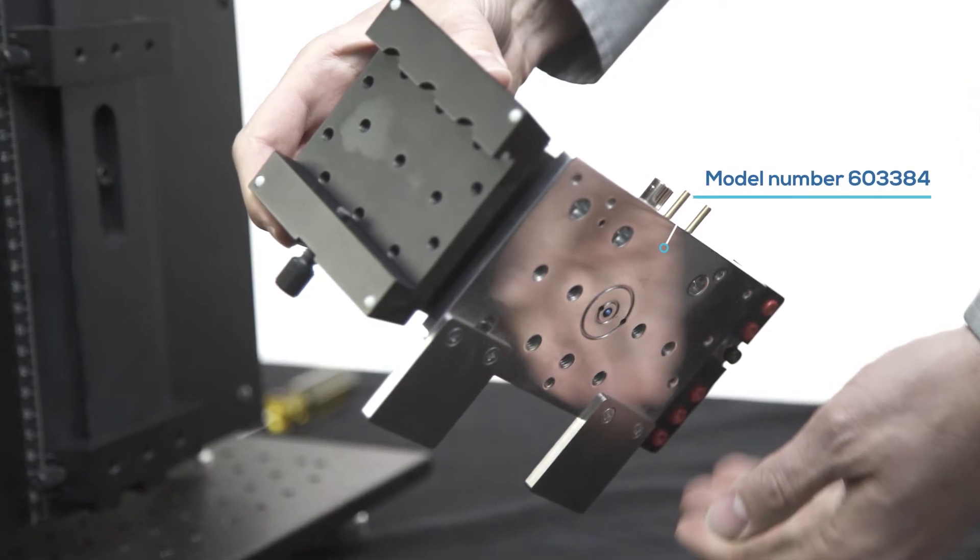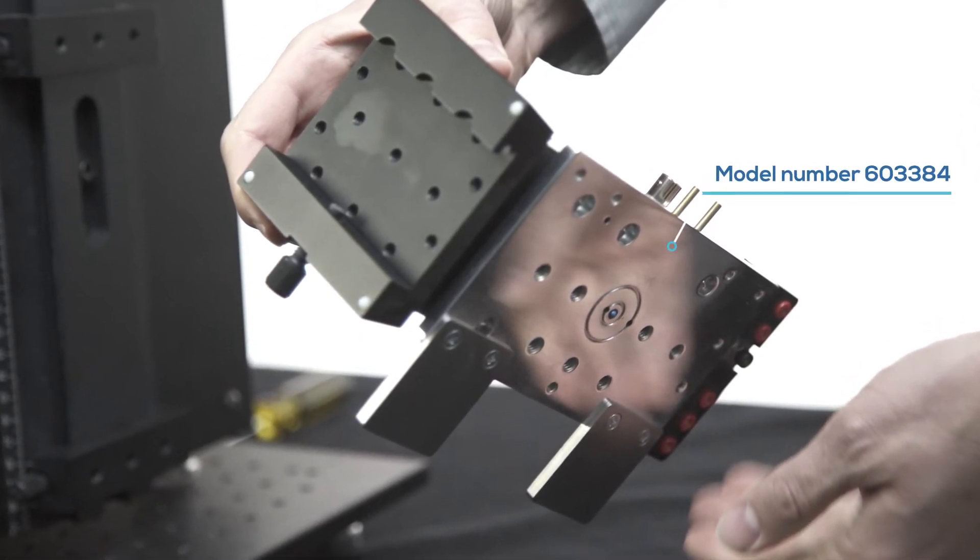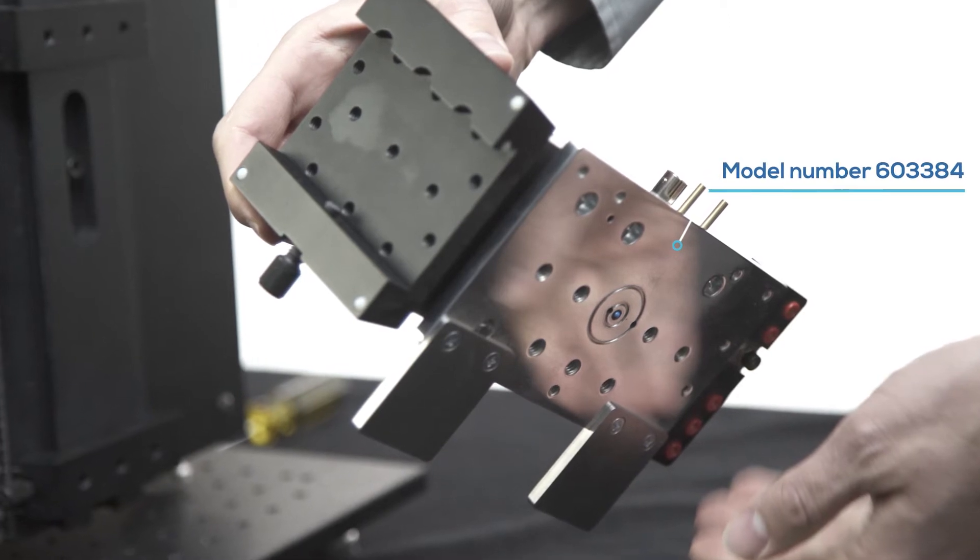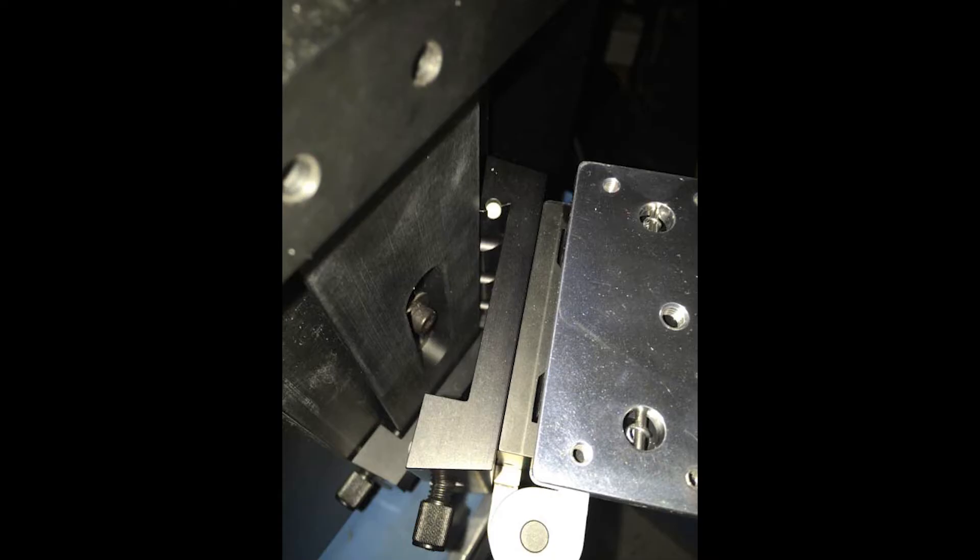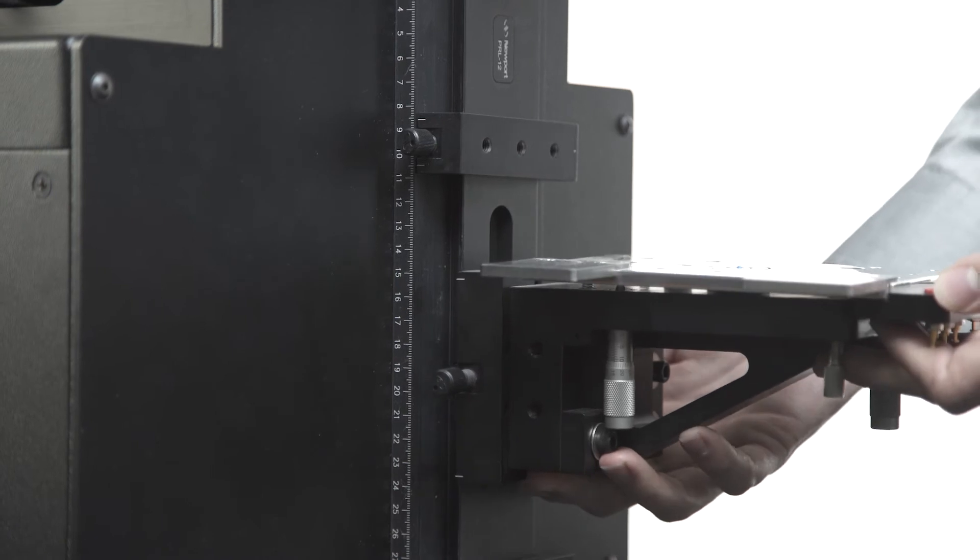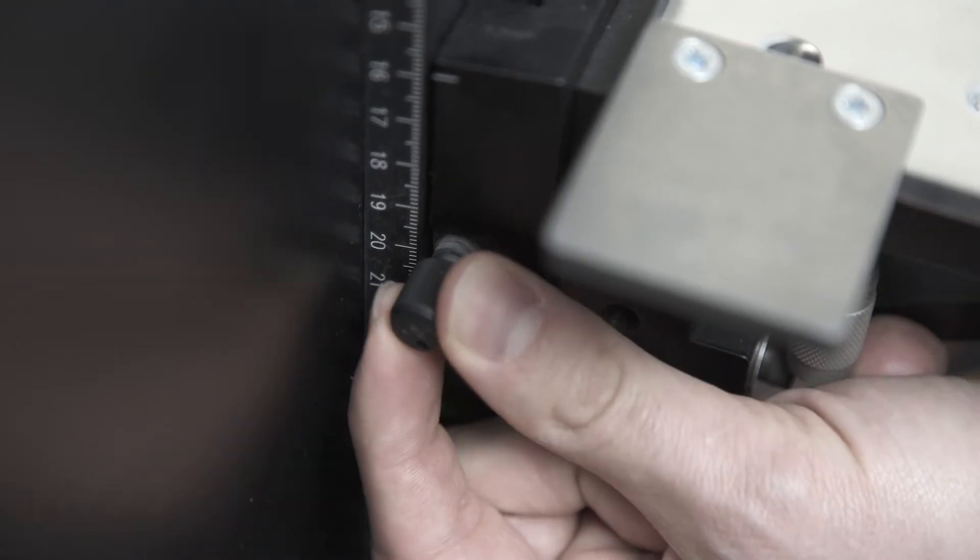We start the setup of the system by attaching the sample stage to the slide rail below the output optical assembly. Loosen the thumb screw on the sample stage until the end is flush with the bottom of the V-groove on the inside of the stage. Place the right side of the stage over the right side of the rail, pivot the stage to place its left side over the rail, and tighten the thumb screw to secure the stage.